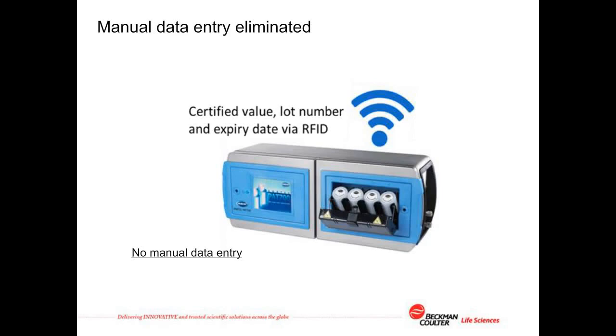Calibration and system suitability standards certified values are contained in an RFID tag in the base of the standards bottle. This data is read by the PAT700 when the standards are placed into the calibration bay, thus eliminating manual data entry. At the same time, the PAT700 checks that the standards are still in date and that they're inserted in the correct order in the calibration bay.